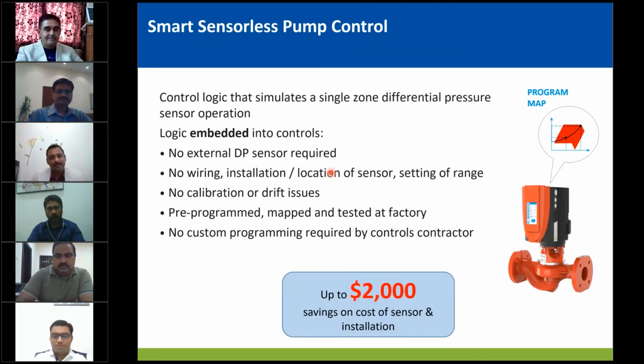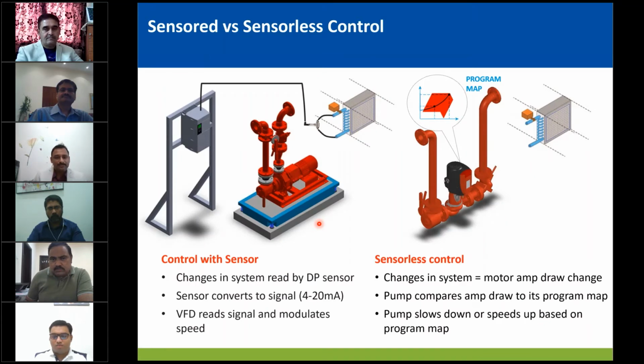Now that's why you will have a lower installed cost, or initial cost, even by having a smart pump. So it has to be looked at as a holistic approach to cost reduction for the project rather than equipment to equipment. Now coming to the traditional way of control and how a sensorless control works. Just an overview. On the left, the sensored system, which is the DP sensor. We talked about the locations. So the DP sensor reads the value and sends a signal back to the variable speed controller in a 4 to 20 milliamp signal. So this 4 to 20 milliamp signal is read by the variable speed drive, and the variable speed drive modulates the speed to achieve the provided set point.